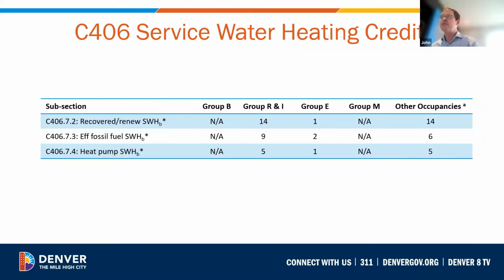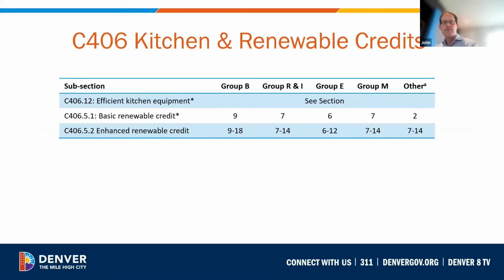Heat pump water heaters are an effective means of heating water and are rated with an energy factor. A new credit is available for projects with heat pump water heaters with a weighted average efficiency of 3.0. To avoid drawing heat away from occupied space, these systems should not be located in the conditioned building envelope unless the cooling effect is desired. A parking area, garage, or mechanical closet with adequate space for venting are acceptable locations. Projects can claim specific energy credits for efficient kitchen equipment as well.